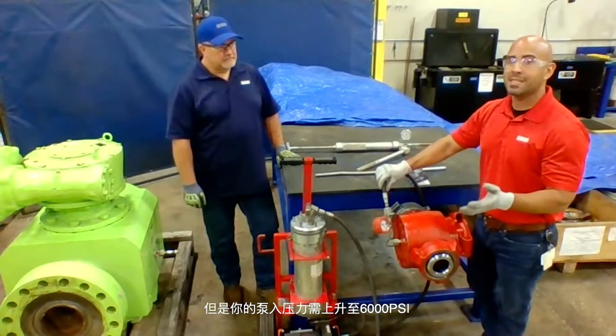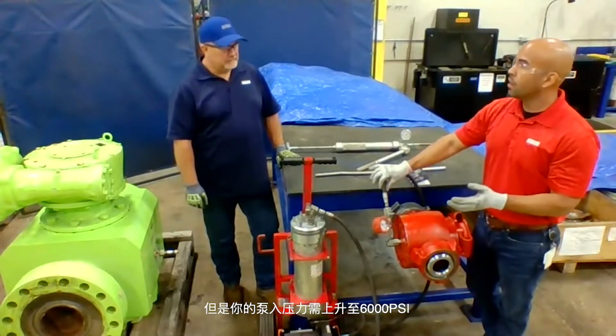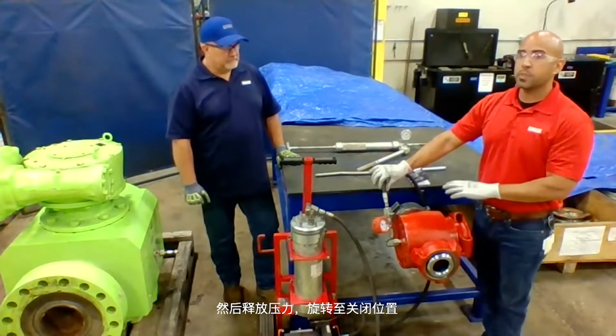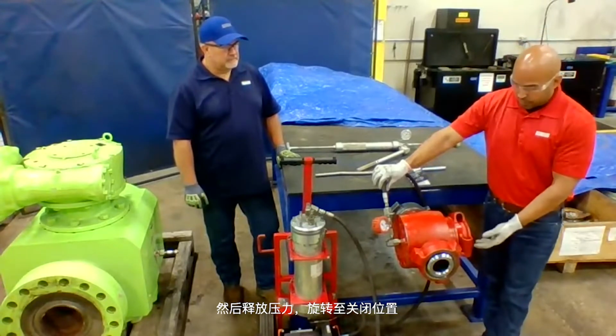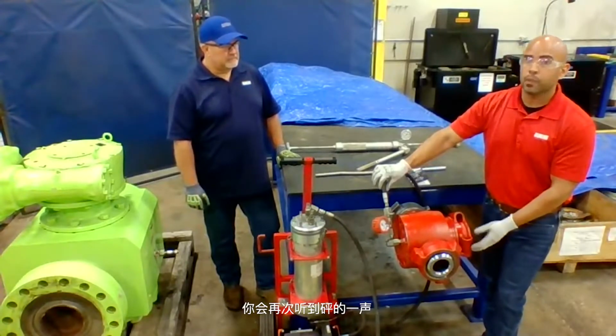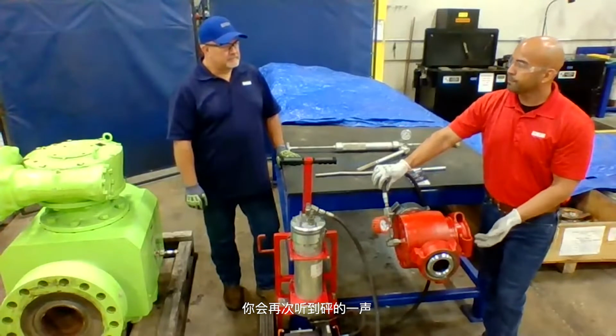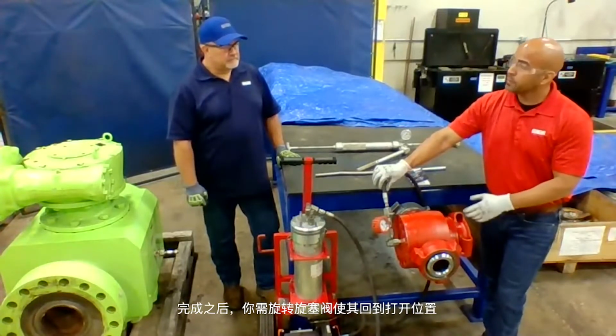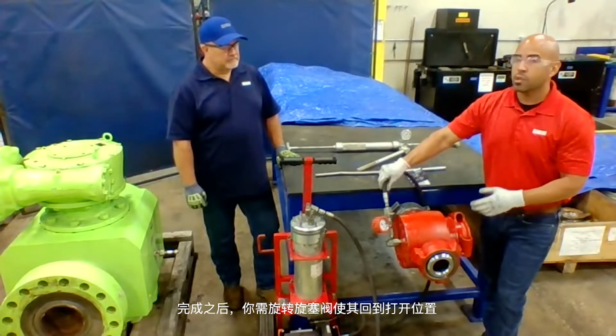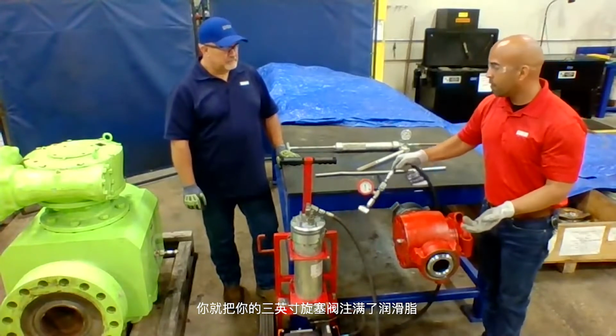However, you're going to go up to 6,000 psi on your gauge. You're going to release pressure, bring it back to the closed position. You're going to hear a popping noise again. After you've done that, you'll cycle it back to the open position. You've then fully greased your 3-inch plug valve.